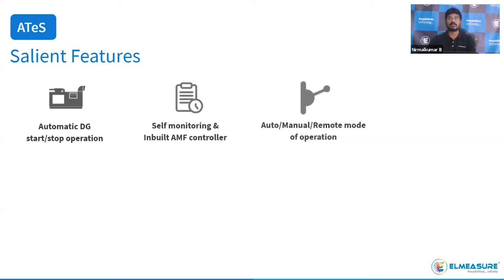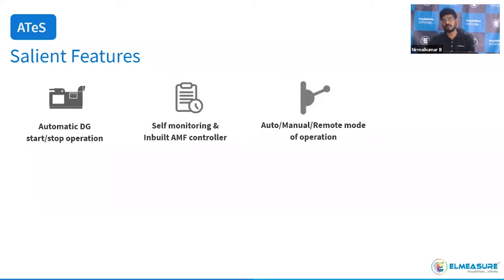The third mode is remote mode, available in three options: control via the remote display; RS-485 communication, through which the customer can integrate the system to the cloud and an EMS system; and SCADA or EMS integration for remote controlling and monitoring. So we have auto mode, manual mode, and remote mode with three sub-features: remote display, cloud connectivity, and SCADA or PLC operation.